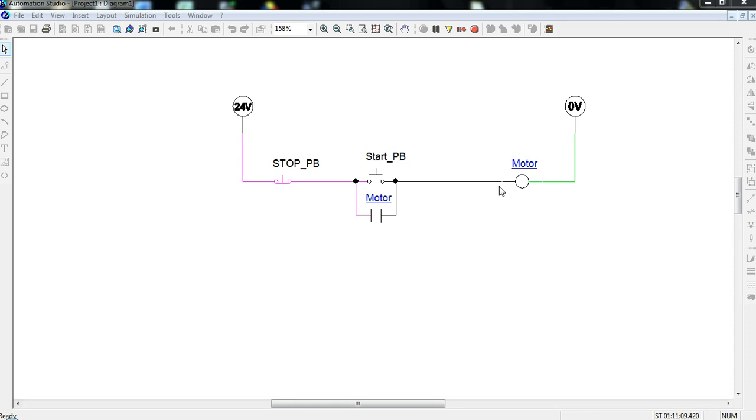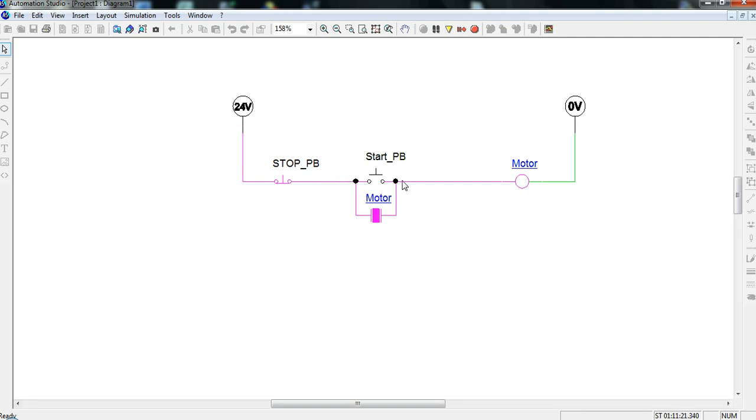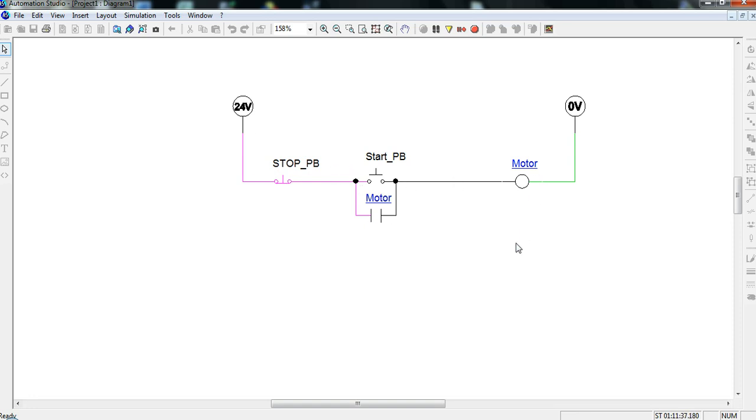The way this circuit works is that when I press the start button you can see it's gone to pink here. It will energize this motor and now I can let go of the start button and I have an alternative path in order to energize the motor. So I don't have to hold the start button to keep the motor going. It can take this path here. The only way to de-energize the motor is if we press the stop button and there you go, it opens it up and now there's no path for the current to get to the coil to energize it. So once again we start it, we energize it, here's our seal. That is called your seal.